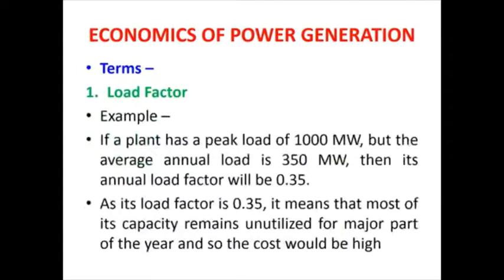Now we will take one example. If a plant has a peak load of 1000 megawatts, but the average annual load is only 350 megawatts. So the plant has a peak load of 1000 megawatts, equal to the installed capacity, but the average load is only 350 megawatts. Then its annual load factor becomes 0.35. As its load factor is only 0.35, it means that most of its capacity remains unutilized for a major part of the year, and therefore the cost of generating the electrical power will be higher.